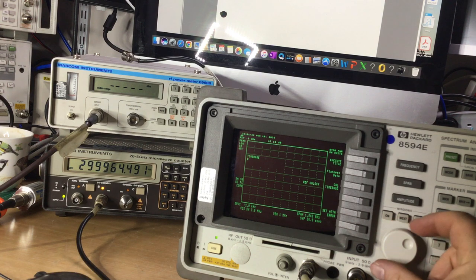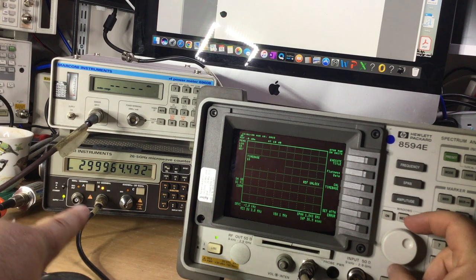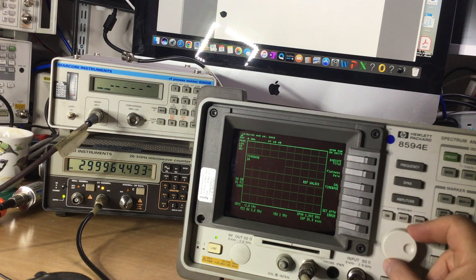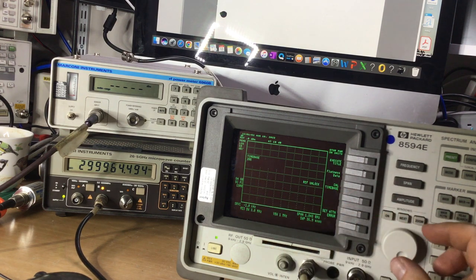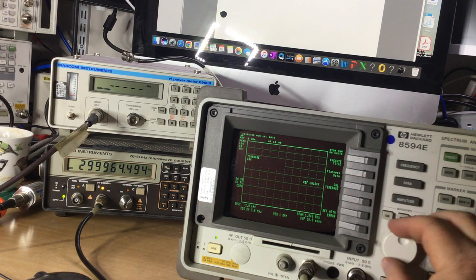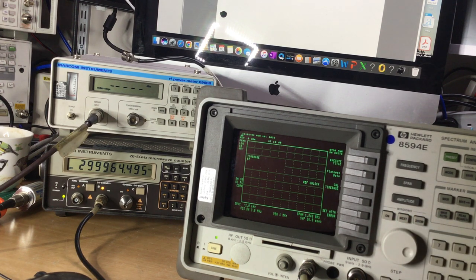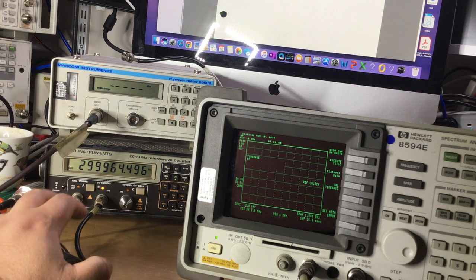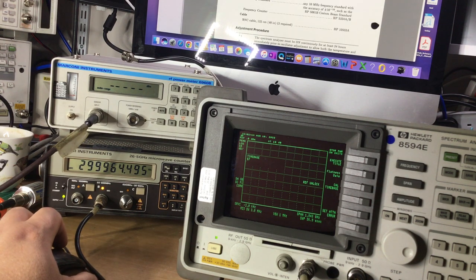And we're going right the way down now to zero DAC, because its range is only 0 to 255. And as you can see, the frequency is actually not moving. It's staying where it is. Likewise, we're now climbing the DAC towards the 255 mark, and we're not even getting tens of hertz in resolution change. So again, we're climbing up now to nearly 255. That's 255. Can't go any further than 255. So making this adjustment isn't actually adjusting anything on the time base. That's a disappointment. Looks like there's obviously a fault in the time base circuitry, something of that ilk. So might need to look at that further.